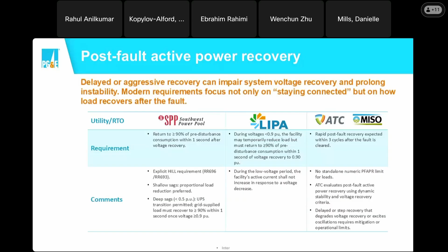There are other utilities that require the same thing, but in a very different kind of fashion. So if you look at ATC, for example, they are looking for post-fault recovery within 3 cycles after the fault is cleared. They don't specify what voltage threshold beyond which you need to recover. So you can think of that as either flexibility or non-flexibility, depending on the type of system that you're operating with. So these are some of the things that we are trying to define as part of the work that we're doing as well in our study plan. If you can go to the next slide, please.